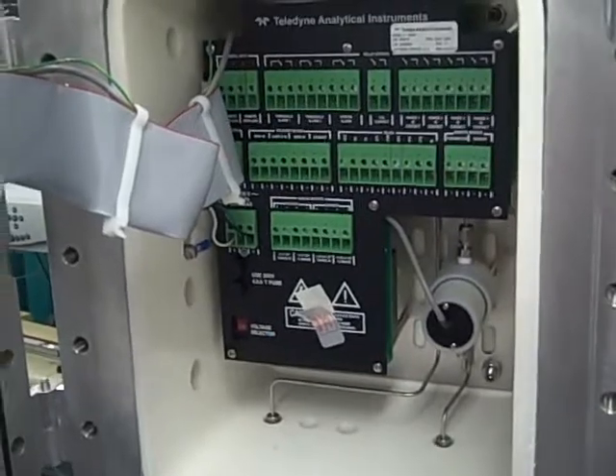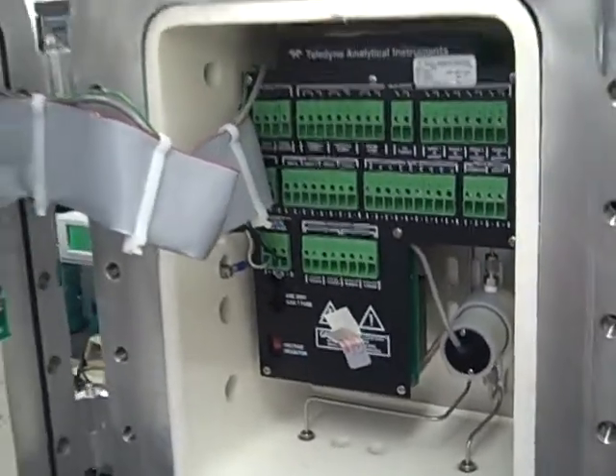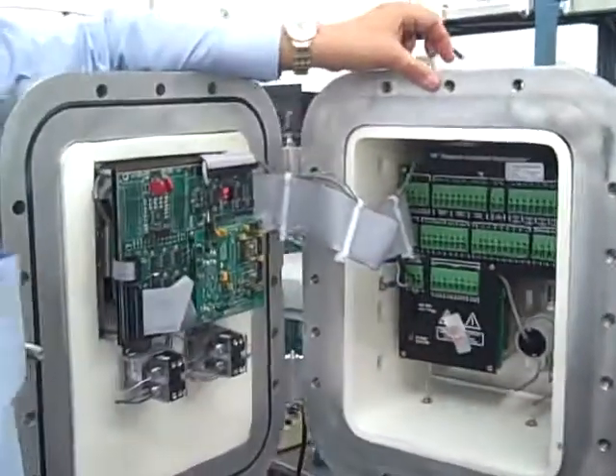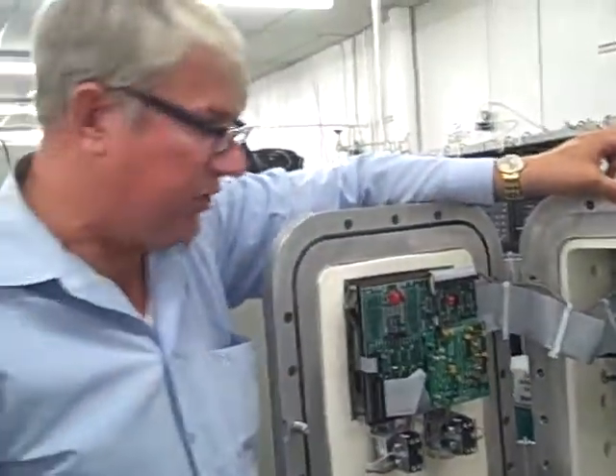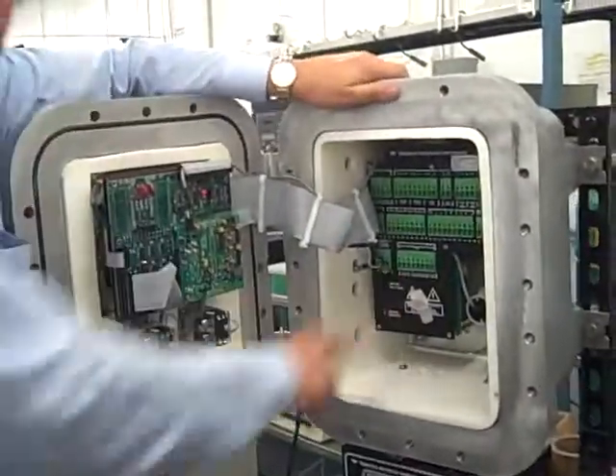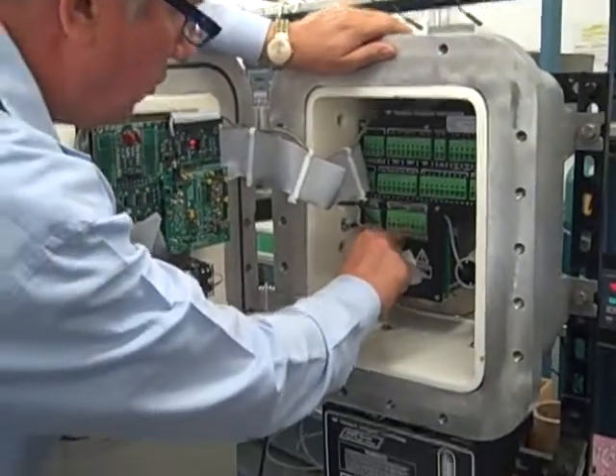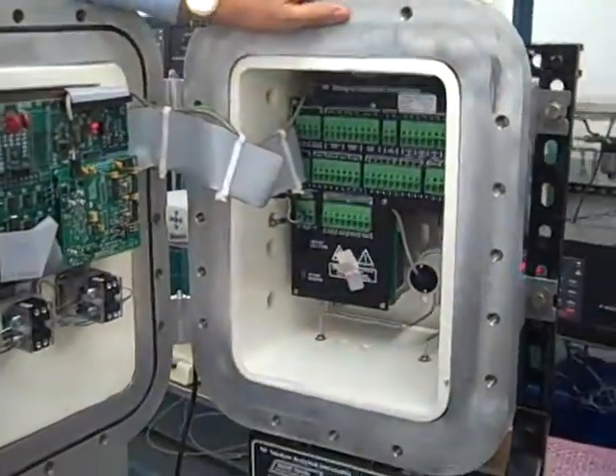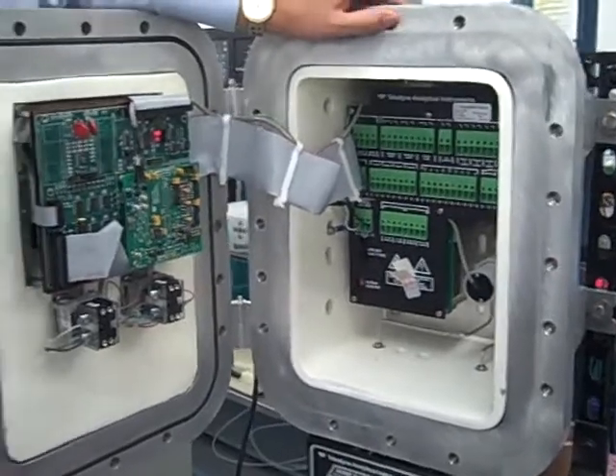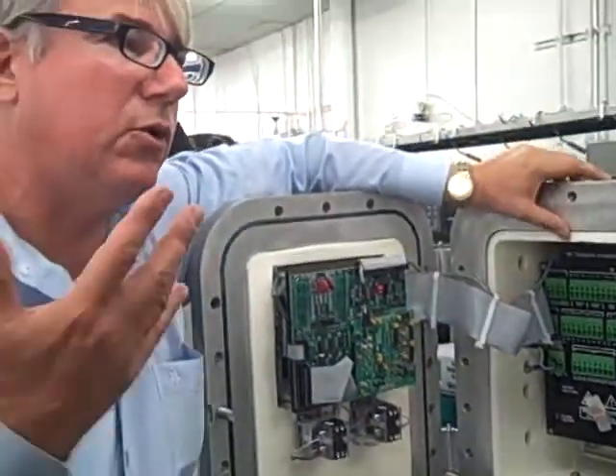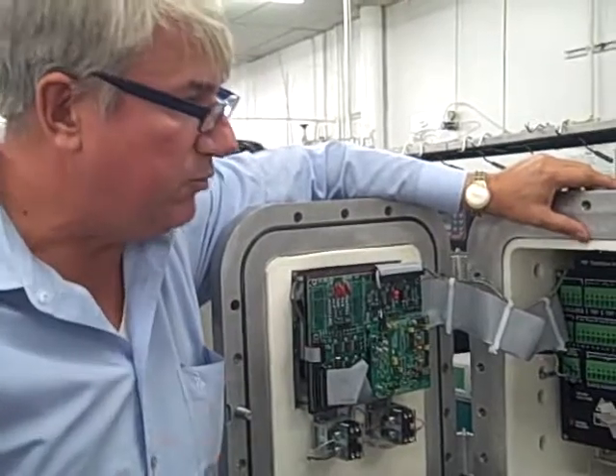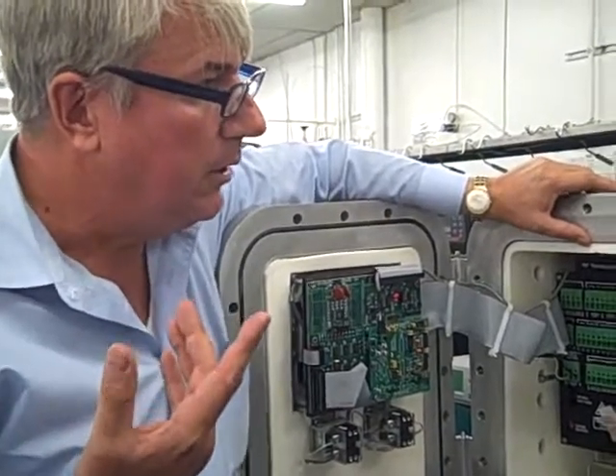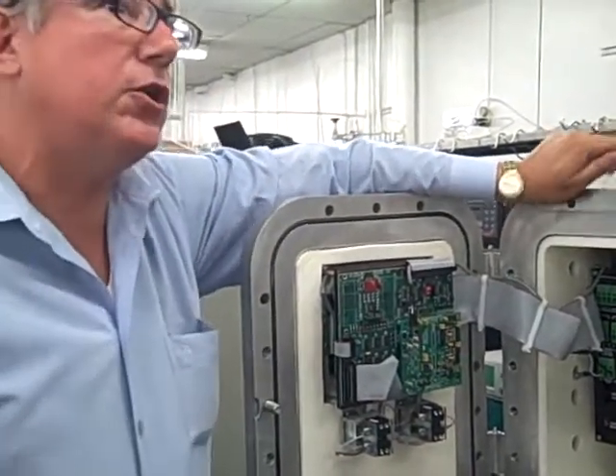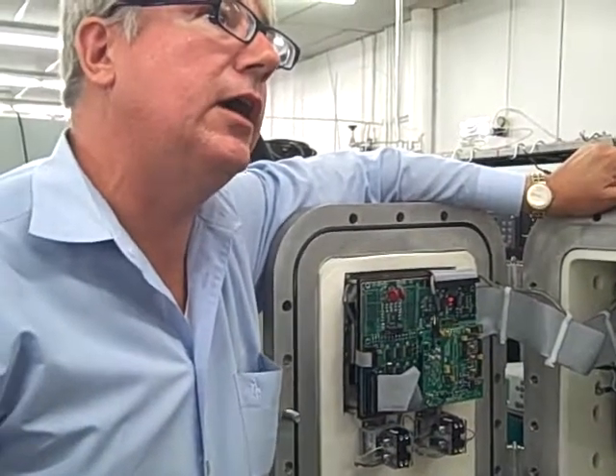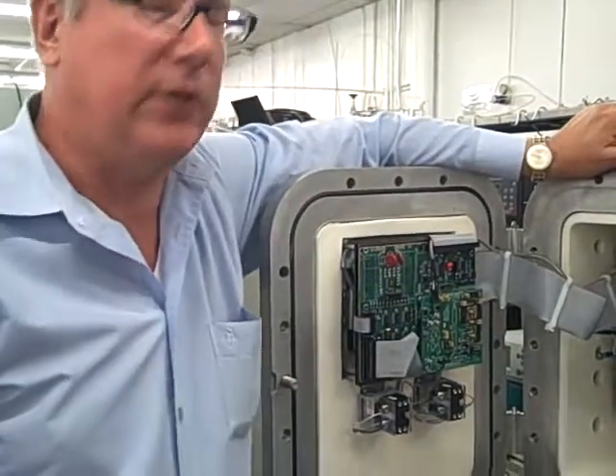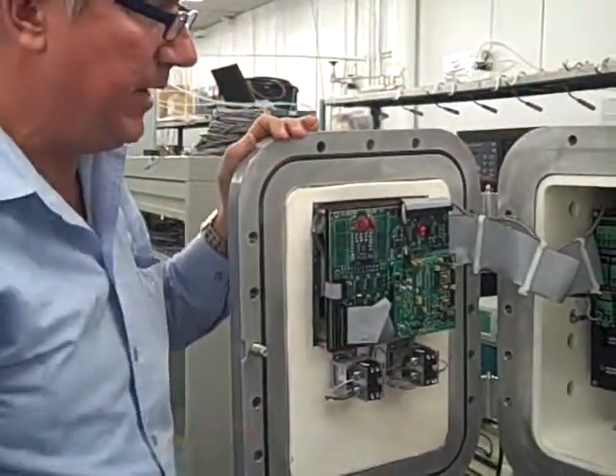So for instance, if you were working on a 0 to 10% range and you had a reading of 5%, then you'd have a half a volt on your percent of range indicator. Also, we have a 4 to 20 milliampere output that gives you a percent of range indicator also. So for the sake of example, again, if you're on a 10% range with a 5% reading on the display, then the current you should get would be 12 milliamps, I believe. Is that correct? That's correct. Okay. Did my math correctly this time.